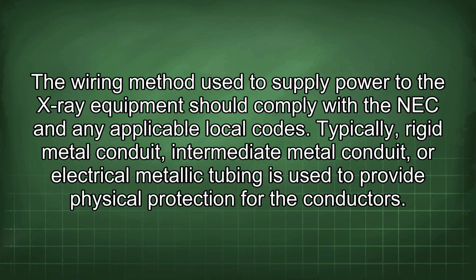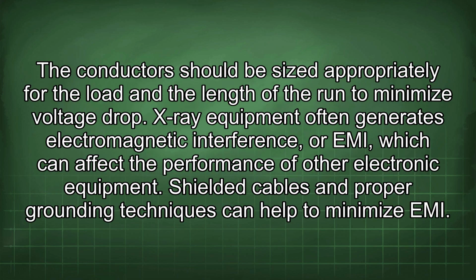The wiring method used to supply power to the X-ray equipment should comply with the NEC and any applicable local codes. Typically, rigid metal conduit, intermediate metal conduit, or electrical metallic tubing is used to provide physical protection for the conductors. The conductor should be sized appropriately for the load and the length of the run to minimize voltage drop. X-ray equipment often generates electromagnetic interference, or EMI, which can affect the performance of other electronic equipment. Shielded cables and proper grounding techniques can help to minimize EMI.